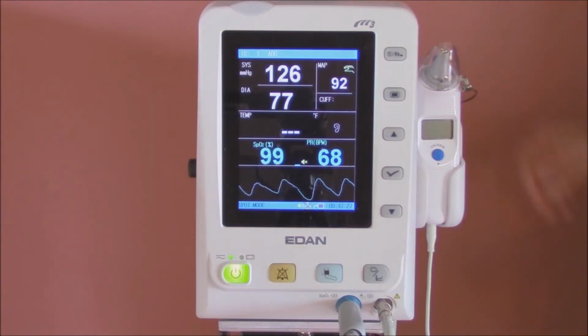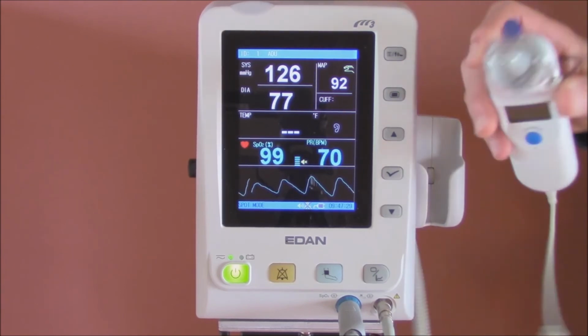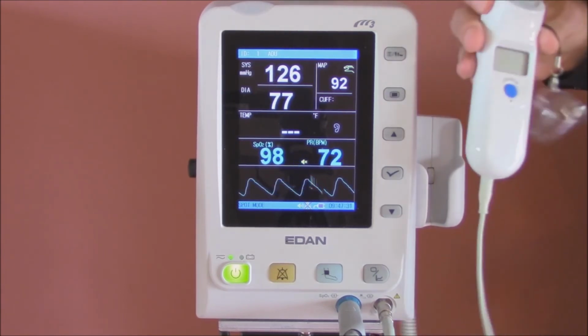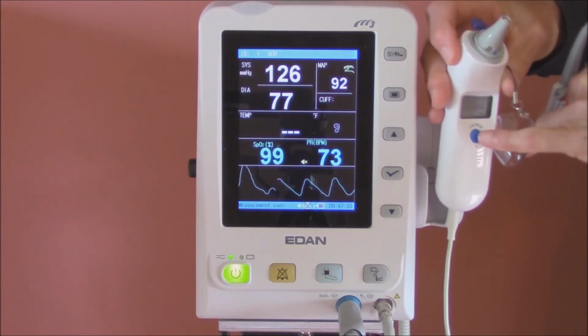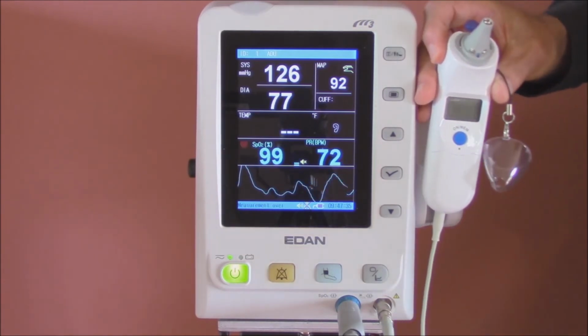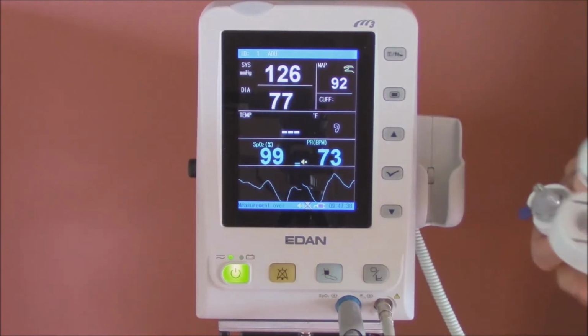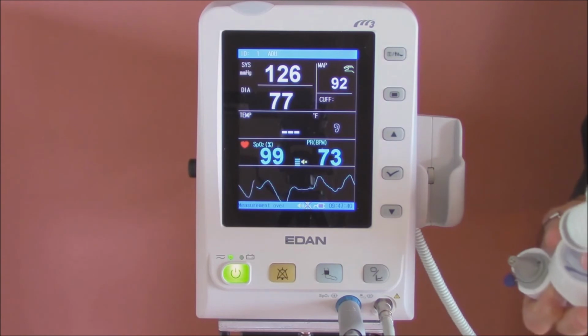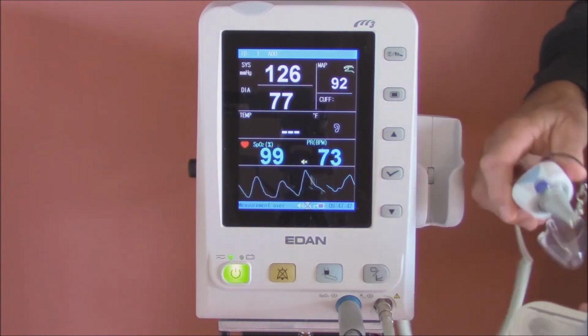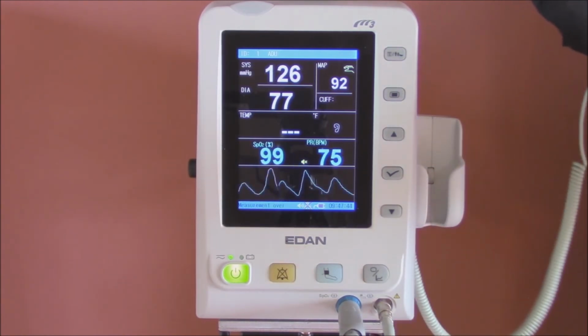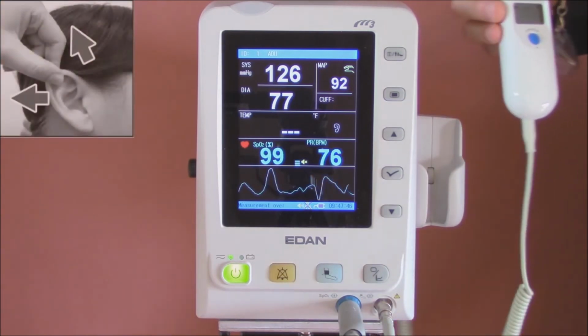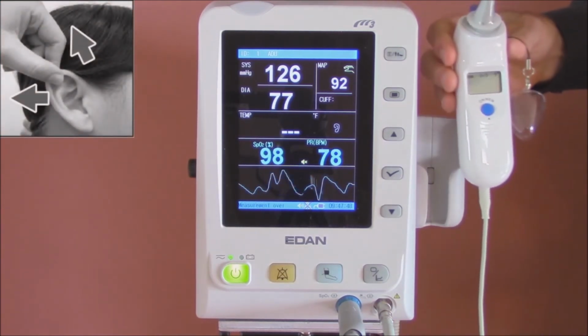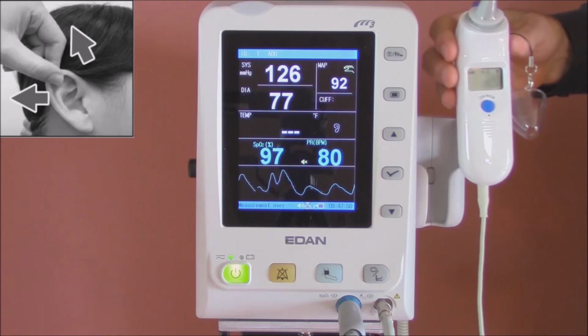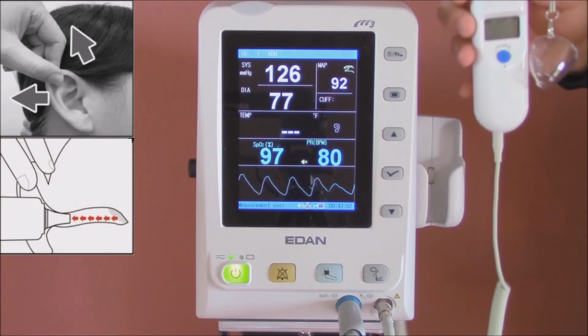For the tympanic thermometer configuration, remove the cover by pressing forward on the blue release tab. Turn the probe on by pressing the blue On Memory Switch button on the underside of the probe. Take the tympanic cover dispenser and slide the tube over the cavity to dispense a cover. Press the tympanic thermometer probe into the cavity to place the cover on the probe. Gently pull on the resident's earlobe as shown to straighten the ear canal and insert the probe into the ear canal as far as it will go.